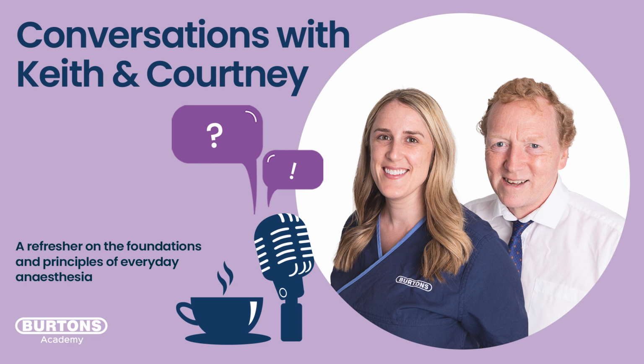The transducer's got to be set up, it's all got to be flushed through so we've got no air bubbles, and we've got to understand the procedure for zeroing. I think that's probably one of the last things to do. So do you want to talk through the zeroing process?